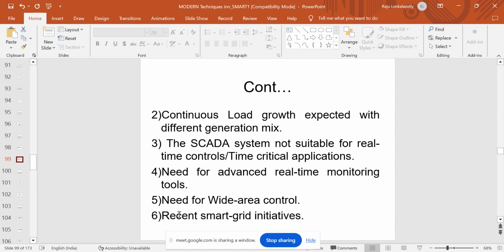How to make it approximately 1 per unit? That is, when you have nearby shunt capacitors, sitting at the load dispatch center, I can switch on the shunt capacitor. These things we call real-time control. Therefore, the SCADA system is not suitable for real-time control or time-critical applications, because SCADA is an analog device, and there will be some delay in capturing one measurement after another. Even though today some delay exists between measurements, we are not considering it. Therefore, we require the PMU, the phasor measurement unit.